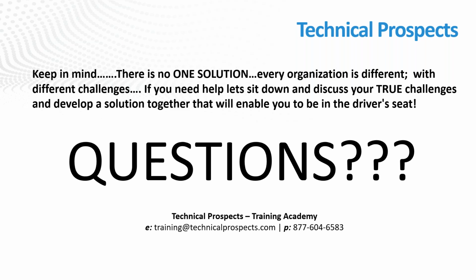Our next question is, as we move toward in-house programs, is there a way to determine how many imaging engineers we need and the required training? That's a great question. Part of the services that we offer is labor utilization analysis. It starts with understanding first the patient flow in the hospital, the ancillary services, the imaging department, and their actual coverage period.